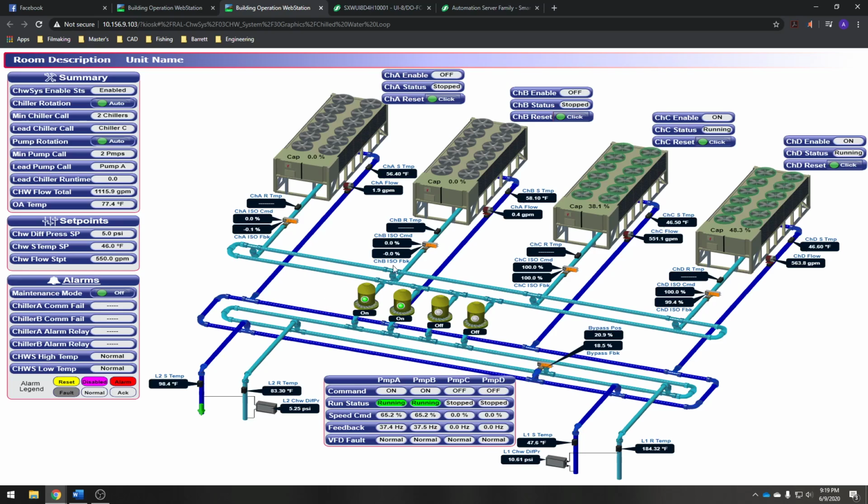So getting back to it, we talked about why we installed the pumps. It's a variable primary system. We're controlling these pumps. We added differential pressure sensors, flow meters, isolation valves, and a bypass valve as well. The secret sauce of the variable primary system we've discussed is to modulate the pump speed. Okay, how do we modulate the pump speed?